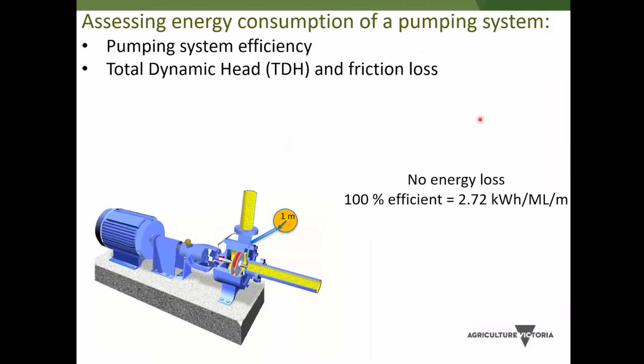When we're looking at the energy consumption of a pumping system, there's two components we need to look at. There's the pumping system efficiency. So that's essentially how efficiently the power, electricity or diesel is being converted into the movement of the water. We also look at the total dynamic head of the system, so the pressure that the pumping system has to work against, and therefore, how hard that pump has to work.